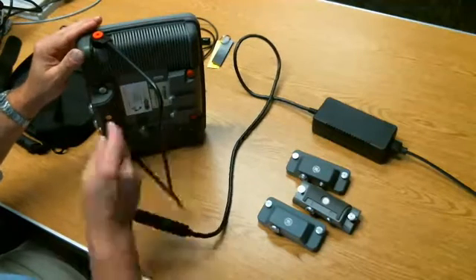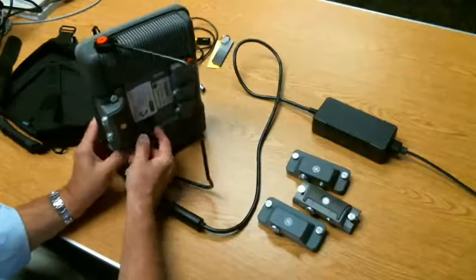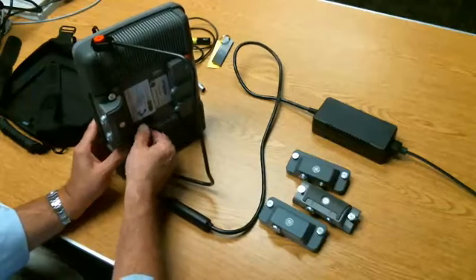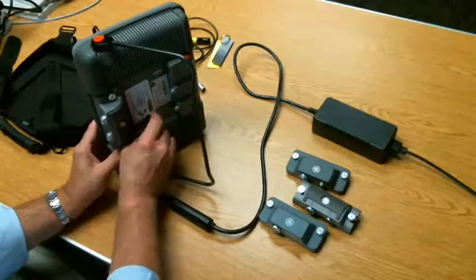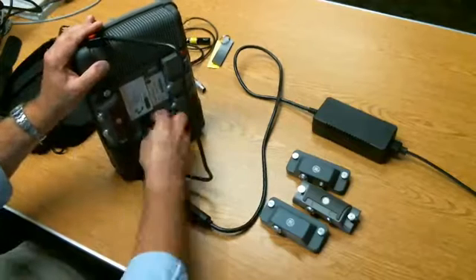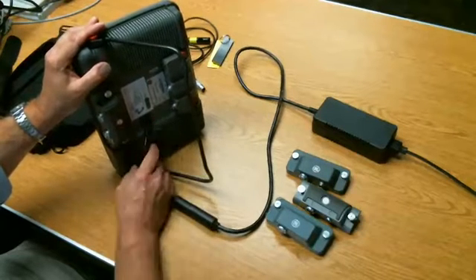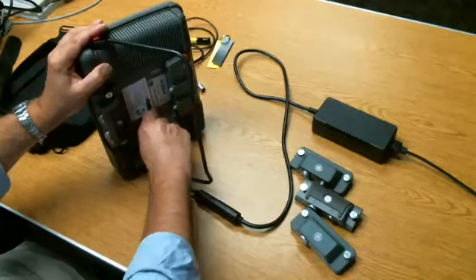The output of the charger goes into the power jack here. It's easiest to turn the instrument on end and just take your finger and give a little spin to the locking collar. That will engage with the connector on the instrument and keep the charger engaged properly. You can do it by gripping the ring with your fingers, but it's a little more awkward. I always set my instrument on end, give it a quick spin, and it locks.